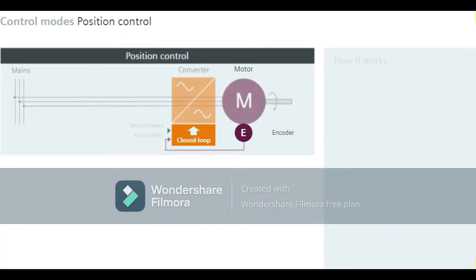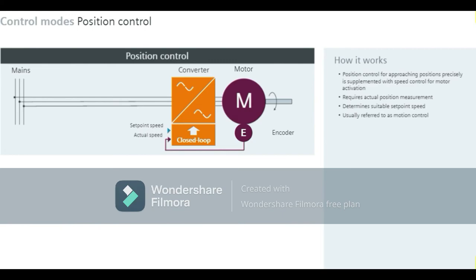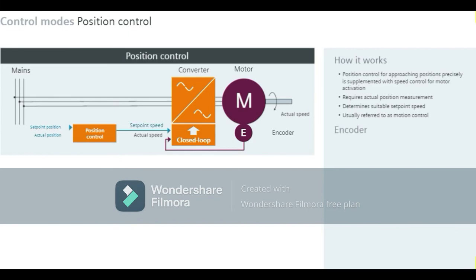Position control is required in addition to speed control if positions must be approached precisely. It is superimposed on speed control and requires an actual position measurement. The position controller determines the right set point speed based on the set point and actual positions. Such applications are usually referred to as motion control. The pulses from the same encoder which provides the actual speed are also used to detect the position via pulse counting, though requirements regarding quality and signal resolution differ.